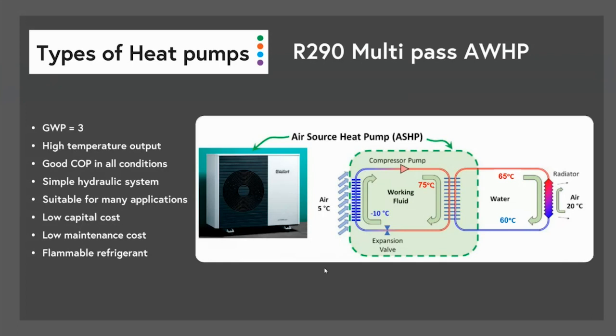So here I'm specifically talking about R290, but more specifically about multi-pass. Multi-pass heat pumps work on a small temperature difference. If we look across on the right-hand side there, producing 65 degrees out to the radiator system, the water's coming back at 60, and it just lifts that 5 degrees and sends it back out again. So R32, R134A heat pumps, all of those existing products on the market all work this way. They're multi-pass units as a general rule, and work on small temperature differentials. The beauty with the R290 is the ability to produce a high temperature on that secondary side, therefore giving us better opportunities to use it for other applications.